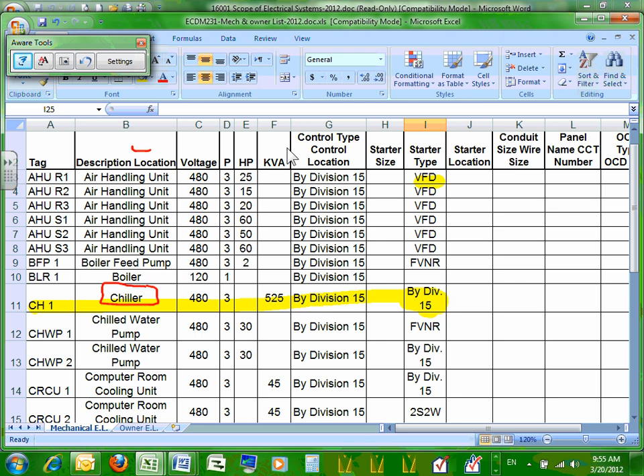Well, would they take the full capacity of the 525 in the winter? Ultimately, your peak largest load is going to be summer anyway, so it's not going to make a difference. And the chiller probably won't work quite as hard in the winter. We're going to have some boiler load in the summer, but if you look at the boiler load, it's really nothing.